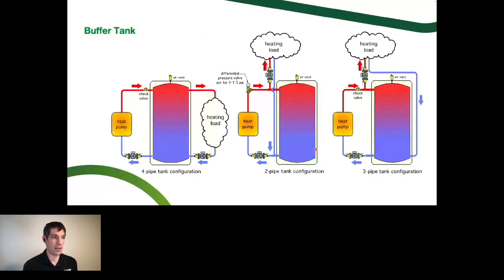How do we pipe these things? The traditional one is like a hydro separator, that we've got 4 ports, just like you would do for a boiler that we showed in an earlier slide, that we've got the supply across the top going out to the system and back. Here are some things that can get a little tricky with the buffer tank.